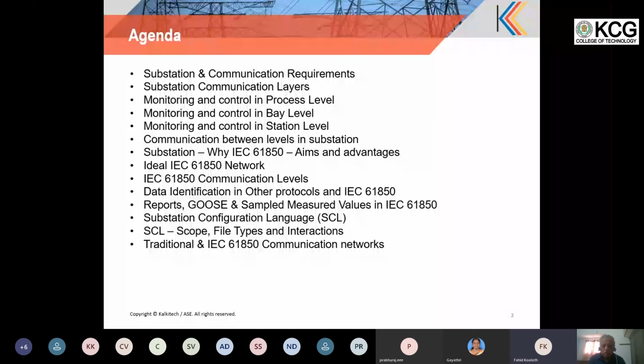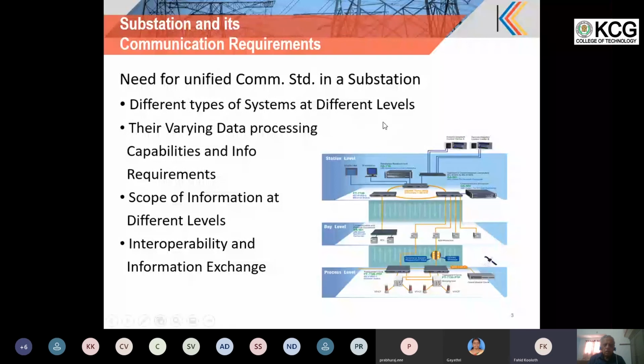Moving on to substation and its communication requirement. There are different levels of substations, and their data processing capabilities at the different levels are entirely different. We can have a process level with the process equipment, CT, VT and circuit breaker. The bay level will have multiple IEDs or relays, and bay level equipment. On the station level, we have HMI, SCADA and other items. So there are three levels: process, bay and station level, and there needs to be complete data exchange between these layers and within these layers. That is the major target in 61850.